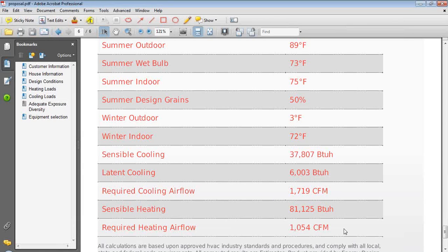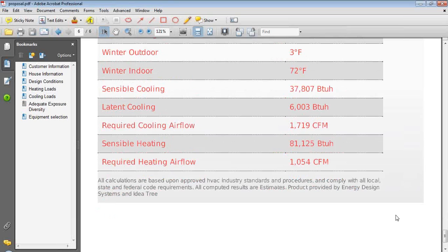So you're not legally allowed to put in something that's more than 15% above these two numbers right here that I'm highlighting. On the furnace side, the number is larger. I think it depends on the kind of system you have, but I think you could oversize it as much as 30 or 40%, I believe. But on the cooling side, not very much oversizing is allowed, because the more oversized you are, the worse your latent performance is going to become, and hence you're going to have humidity problems in the home.